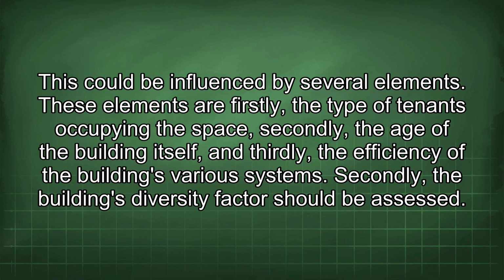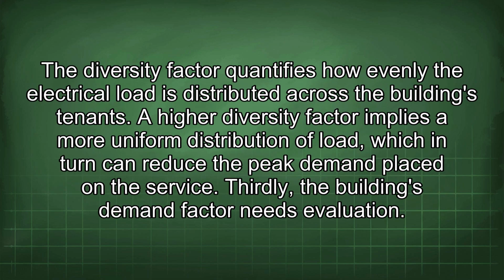Secondly, the building's diversity factor should be assessed. The diversity factor quantifies how evenly the electrical load is distributed across the building's tenants. A higher diversity factor implies a more uniform distribution of load, which in turn can reduce the peak demand placed on the service. Thirdly, the building's demand factor needs evaluation.